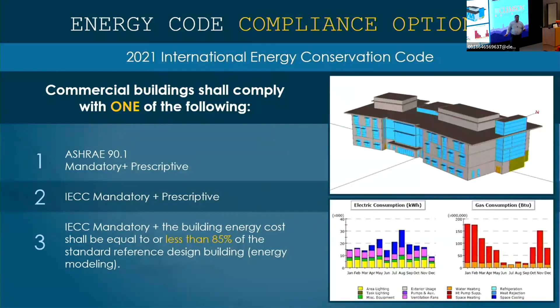That's number 3, and these are kind of cool. Basically you build a model in some software and you say, okay, this is the roof, this is the wall, this is the windows, I have this many people, this many computers, this much lights, I'm going to be open from 8 to 5 every day. And it goes through and does a simulation for the whole year on what it would cost to run and operate this building. If that designed building is 85% of the cost of a code minimum building, then you pass energy code. So keep that in mind. There's various ways to pass energy code, but prescriptive is usually the most common, but you can do an energy model if you're running into some issues.